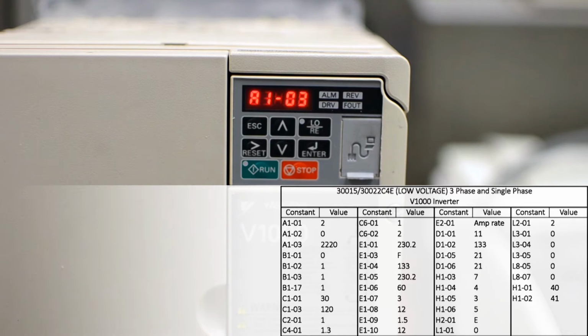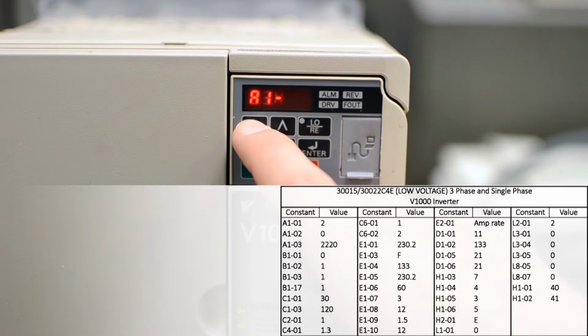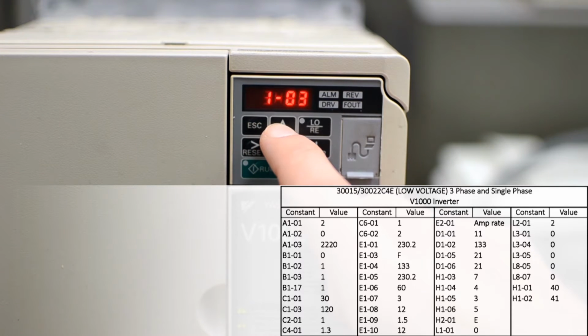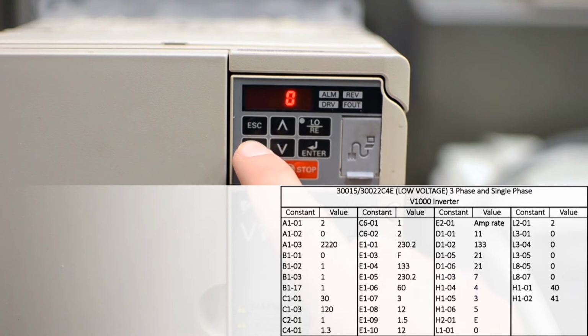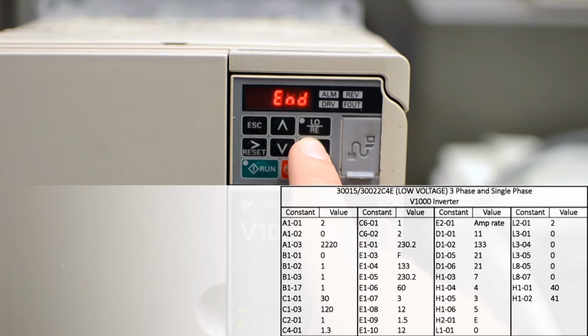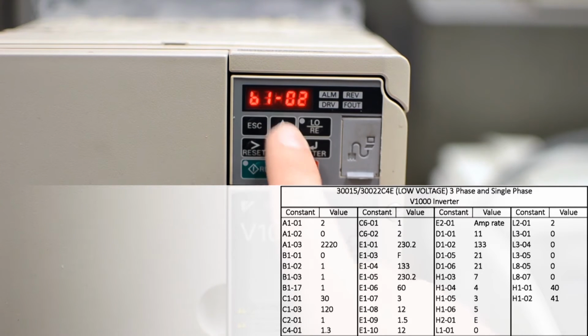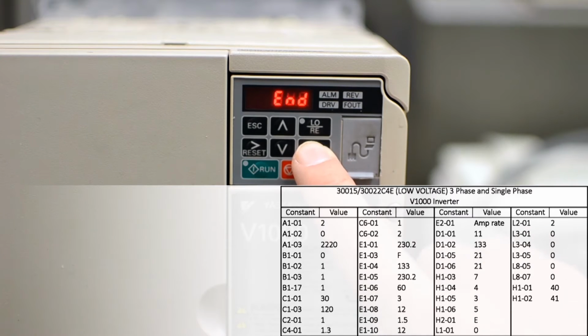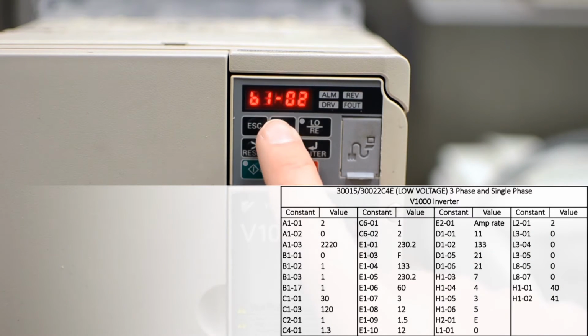Now that I'm done with my A constants, I'm going to move on to my B constants. I'll press the escape key until the A flashes, then I'll scroll up one to the B constants. I'll press enter until I get to B101, then I'll press enter to edit the parameter. So I press reset to move over a digit, change my value, press enter, move up to B102, set my value, press enter, and I'll continue on through B103.